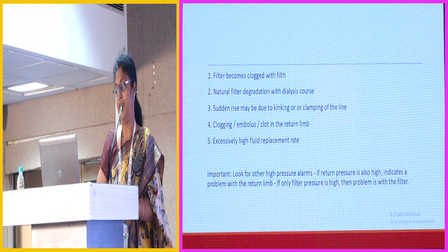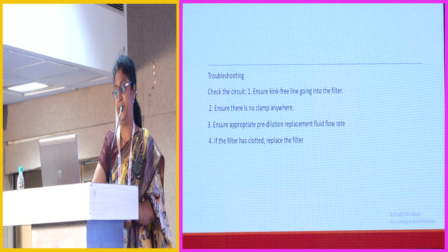Troubleshooting: just ensure it is kink free going into the filter, there is no clamp anywhere, and appropriate pre-dilution replacement fluid. If the filter has clotted, at the end try to replace the filter, which should be the last resort we try, because we should check out all the other reasons first, because the filter is very expensive. We cannot often tell the patients there is some problem and we need to change to a new filter.